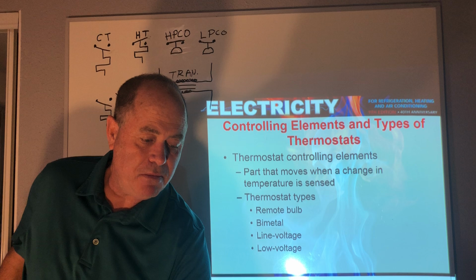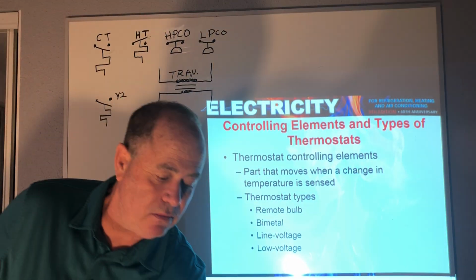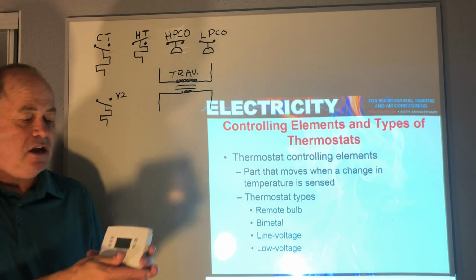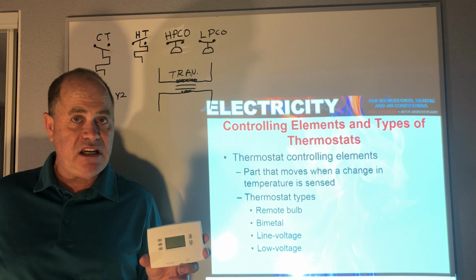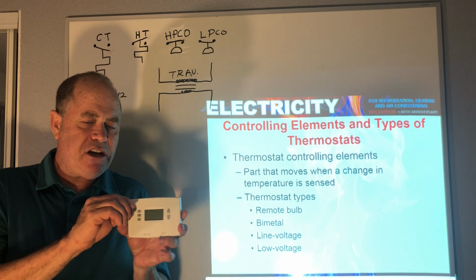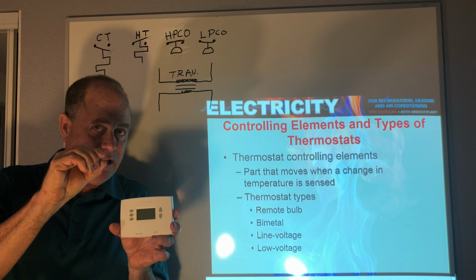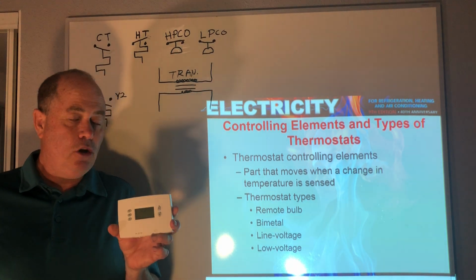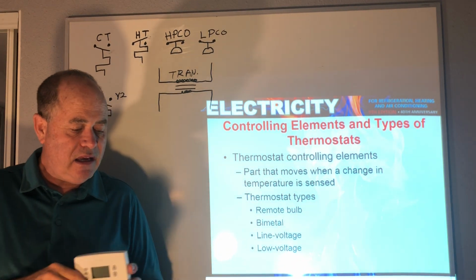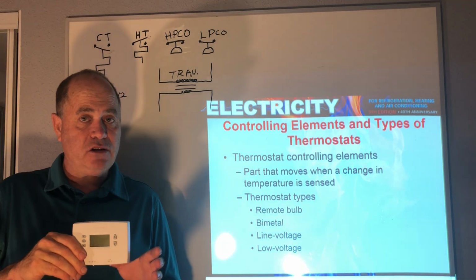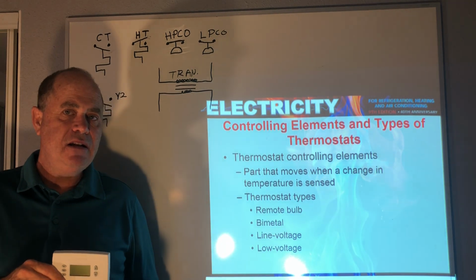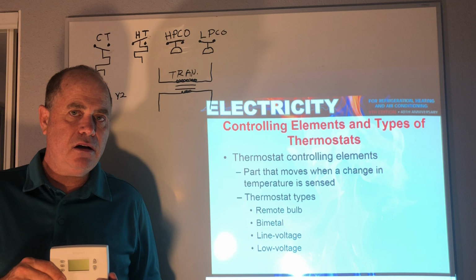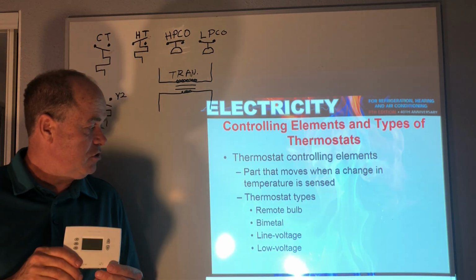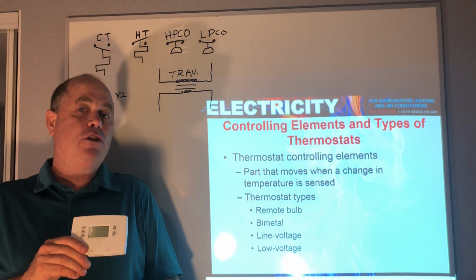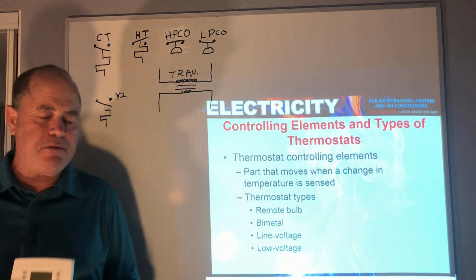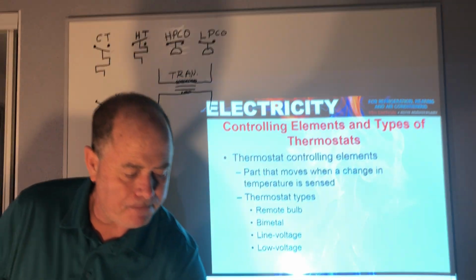But some of the bigger systems that might use a thermostat like I just showed you, like this for air conditioning, that might use 15 amps or so, the little baby contacts in here can't handle that much electricity. So these are low voltage thermostats, and they would control like a contactor, and the contactor would then bring on an air conditioning compressor. So the low voltage thermostat is for larger tonnage equipment, a little opposite of what you think.